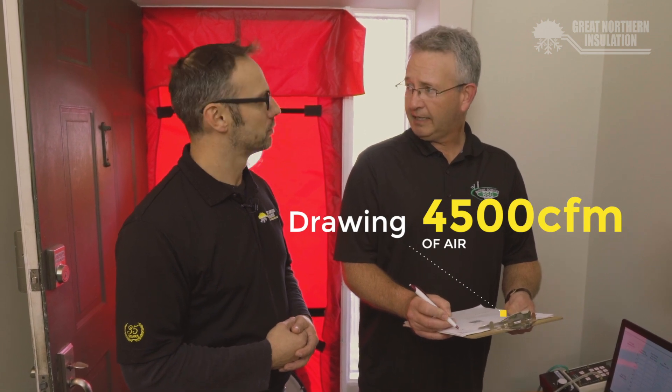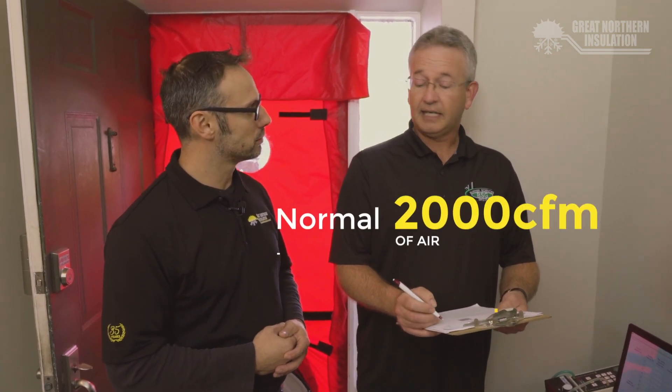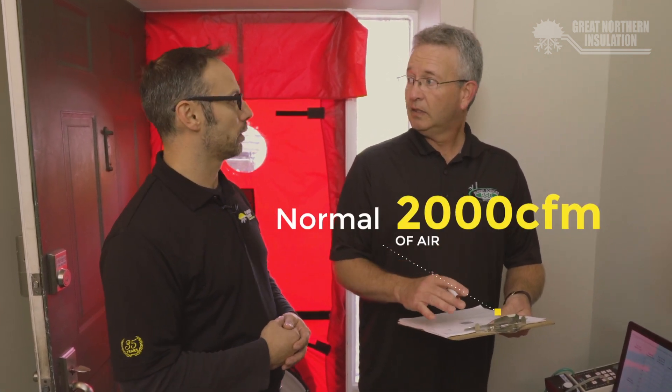Rick, I see that you've finished the first blower door test on the home — what kind of results were you seeing? Well, at minus 50 Pascals we saw that we were drawing out 4,500 CFM of air. Is that a lot? Actually, that is quite a lot. Normally what we'd find in a situation like that is something more around 2,000. So this house is extremely leaky. I did notice on the walkthrough with the blower door running that there was a lot of air infiltration at the ceiling joints and the windows and doors.